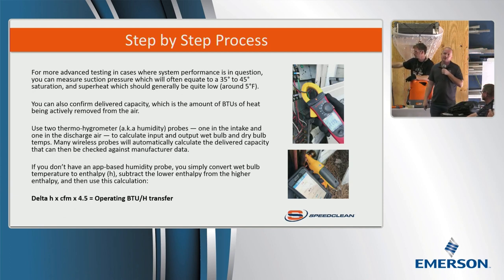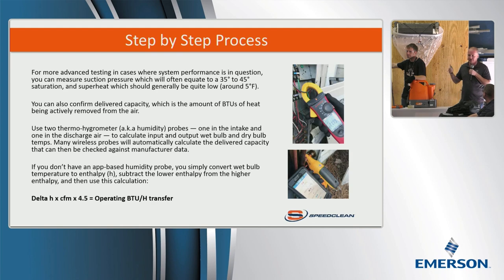But here's the real answer: just use psychrometers and measure quick. Look at the table from the manufacturer on what airflow it's producing at what speed. You're going to want to drive it directly into high speed. Look at the chart. As long as everything's clean, and I've tested a lot of units, it's pretty much going to produce the CFM that's on the chart. The chart tells you it's going to produce 400 CFM at high speed when everything's clean, that's what it's going to produce. You can pretty much trust that. There's no sense doing otherwise. I've used a tach to test it on Mitsubishi and Carrier units, I've used a vane anemometer, a lot of different things, and they all come in very, very close.